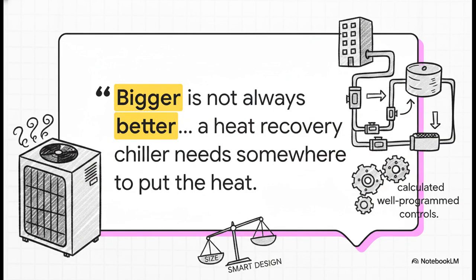Which leads us to this really excellent point from our source material. Quote, bigger is not always better. A heat recovery chiller needs somewhere to put the heat. End quote. I mean, it's a mic drop statement that perfectly summarizes why you can't just buy massive equipment and expect immediate efficiency. Smart, calculated design, well-programmed controls, and perfectly matched loads will absolutely always trump sheer equipment size.